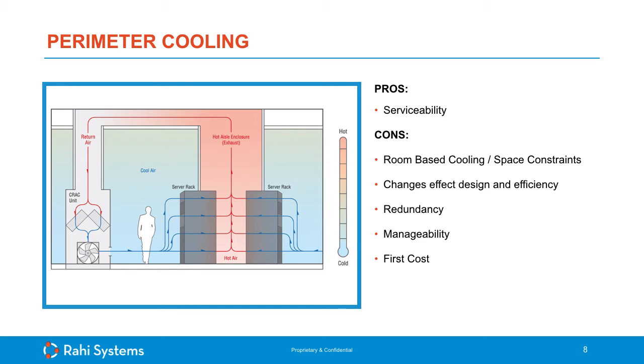So the first one is more of a traditional type of cooling. We call it perimeter cooling, widely used in the data center market. We also call it CRACs or CRAHs, computer room air handlers, computer room air conditioners. It can be deployed in an upflow environment with an overhead ducted system. It can be deployed in a downflow raised floor, and as shown here, it's actually downflow front discharge with hot aisle containment. And actually, that's a very efficient design.